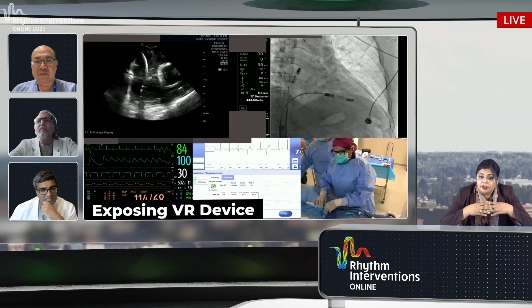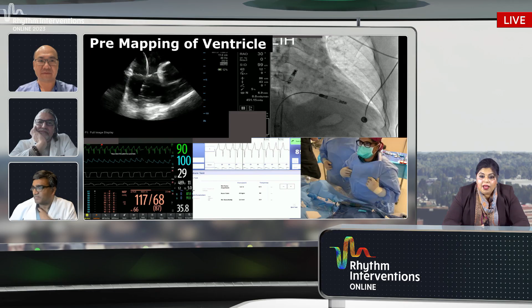And once I'm in good position, I'll take the protective sleeve back, exposing the device there. And at this point, the cathode is exposed. It's in contact, and you can now do the pre-mapping. So just like the atrial device, I almost always do pre-mapping to make sure that I'm in contact with good substrate, that I'm not in a scar location. You can see the injury current. I'll check an R wave. I'll check an impedance. And if I'm patient enough, I'll check a threshold as well. But usually the injury current and the R wave and the impedance is the minimum that I'll do with the pre-mapping.